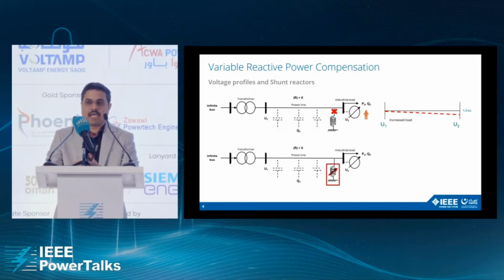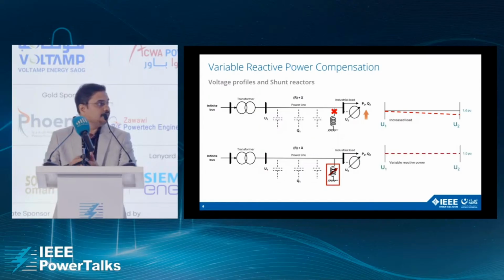An optimum solution will be to have a reactor which can provide variable reactance, or which can absorb variable capacitive reactive power from the system. So whenever there is a change in the load dynamically, this reactor should be capable of dynamically absorbing the power as per the demand, or as per the voltage level instability we can sense from the transmission lines. So under this condition, again, even when we have dynamic demand from the customers, a variable shunt reactor can absorb dynamic reactive power from the network.